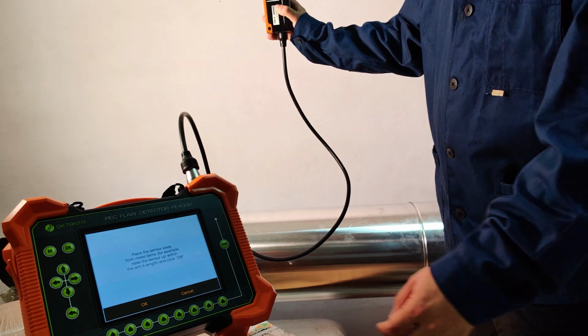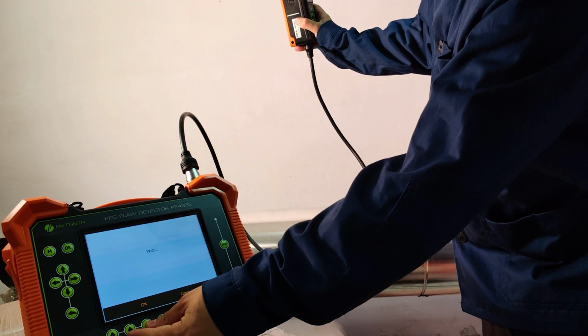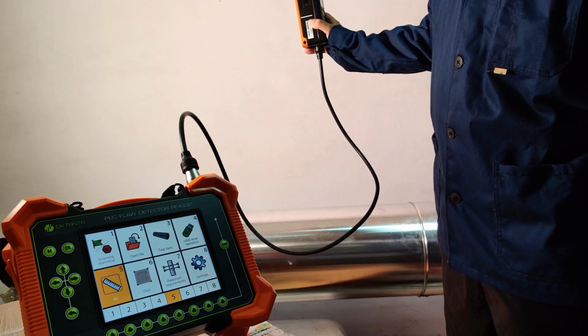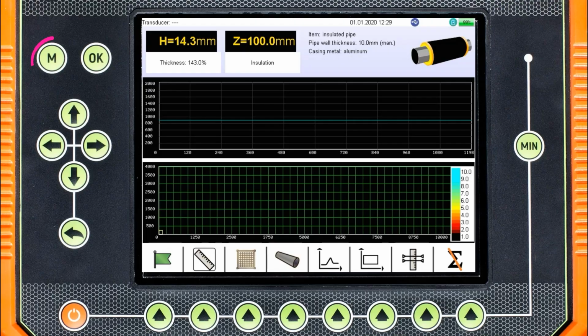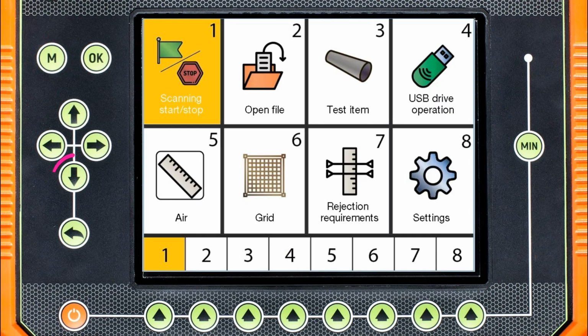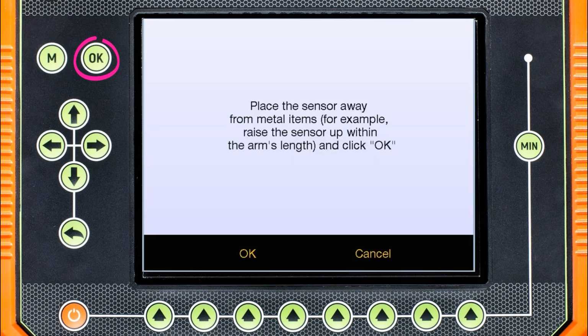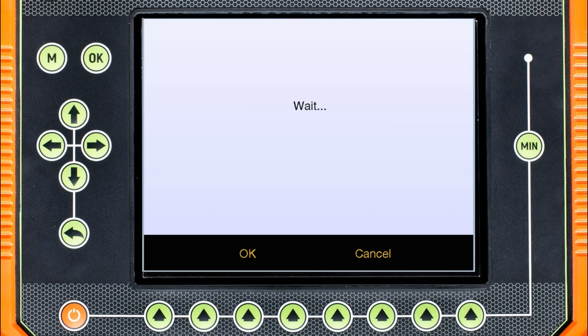Start the air calibration mode. The sensor will be automatically calibrated in no time. You will need to repeat the air calibration of the sensor when replacing it or when the ambient temperature changes significantly, for example, when it either rises or drops by 10 degrees Celsius.